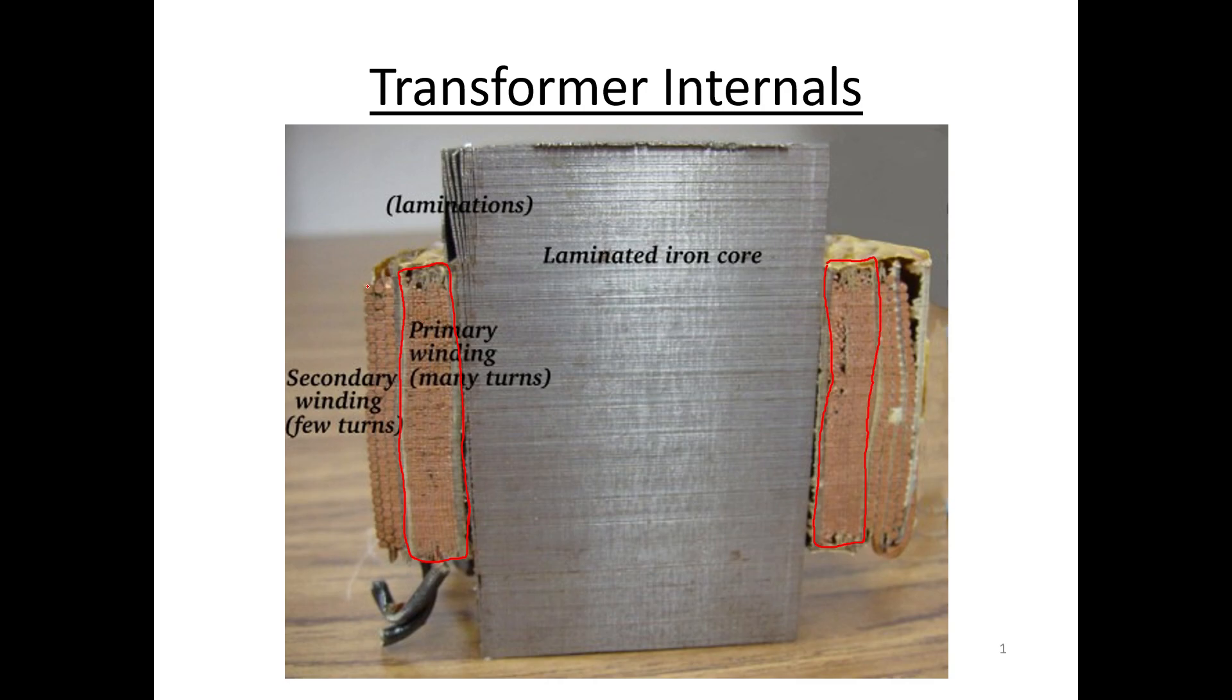Wrapped around, but electrically isolated, you see the little bit of insulation between the two stacks of copper wires. Wrapped around that you have the secondary coils. This is done in a lot of transformers, assuming there's not too much heat that could build up when you've got everything stacked on top of each other like this. This is done so that all of the field lines created by the oscillating voltage that you pipe into the primary winding have to go through the secondary winding, so there is no energy loss in terms of field lines that might not actually pass through the secondary winding.